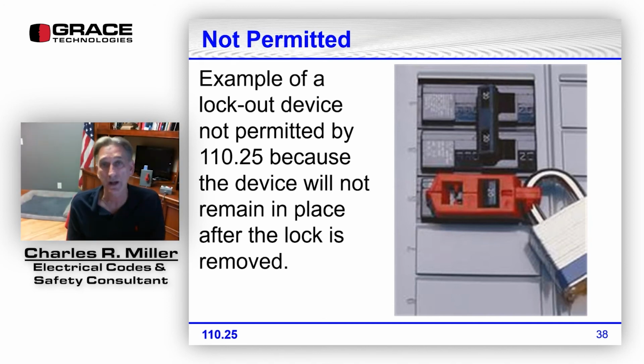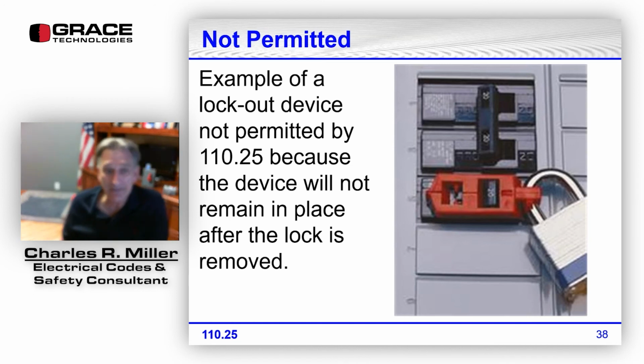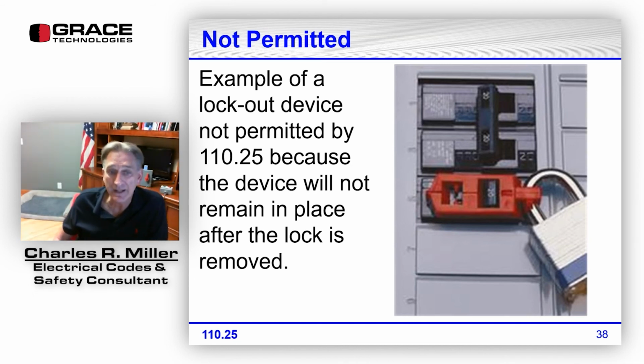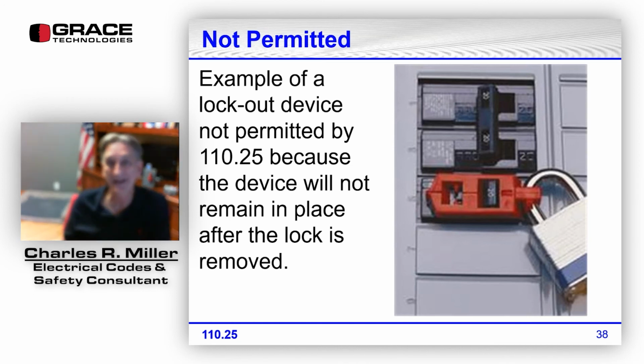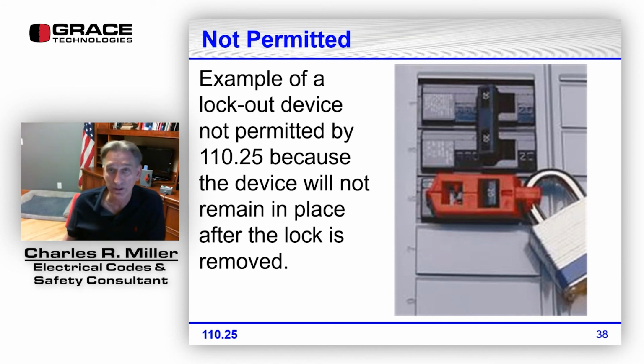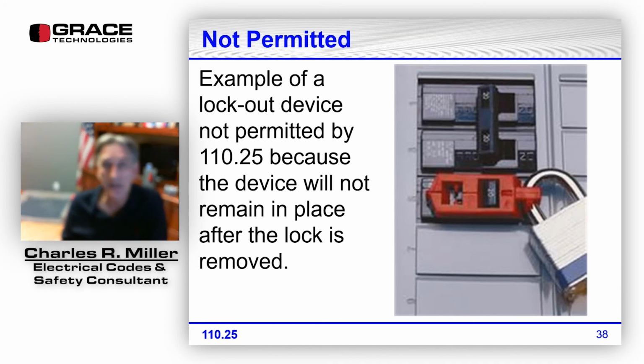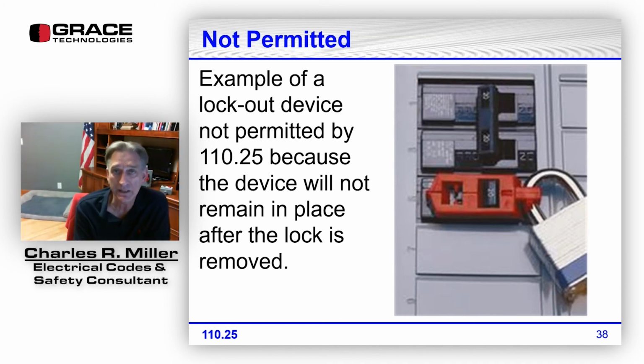I've seen a lot of industrial applications where these aftermarket breaker devices are used for lockout, tagout in accordance with electrical safety, in accordance with 70E, in accordance with OSHA. Yes, absolutely. These are permitted by OSHA. They're permitted by 70E.